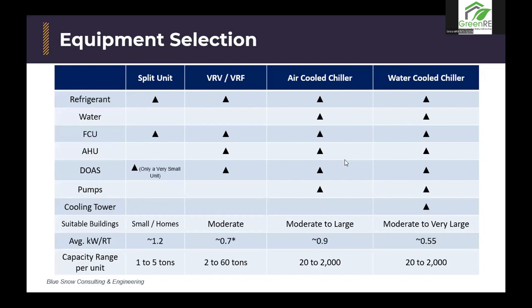So I created a table to show the difference between all the systems that I discussed just now: split unit, VRV and VRF, air cooled chiller and water cooled chiller. The main focus here is the existence of the cooling tower. For the air cooled unit, we don't need the cooling tower, but for water cooled, we need the cooling tower. For suitable buildings, the split unit, as I mentioned, is for small residential homes. VRV, VRF can be moderate, such as offices. Air cooled and water cooled can both be used for moderate and large, but water cooled is available for large capacity as well.